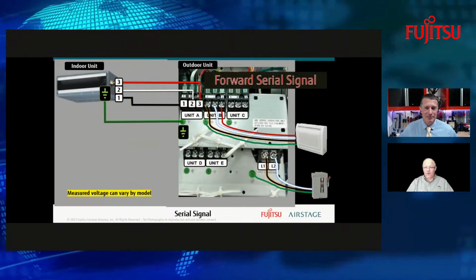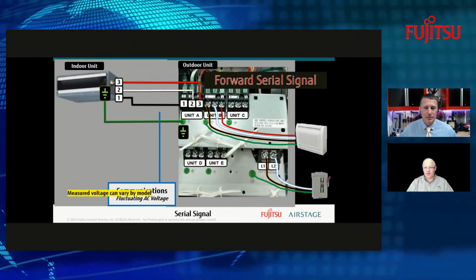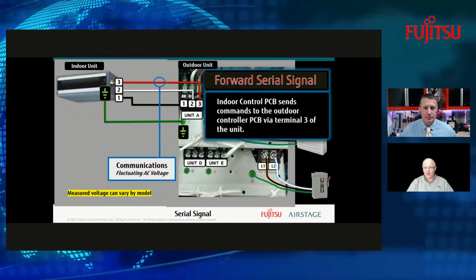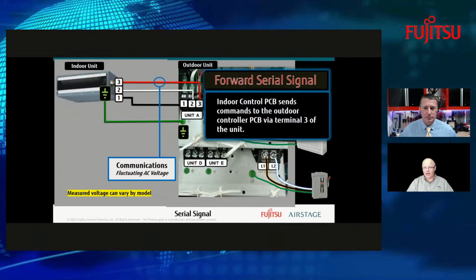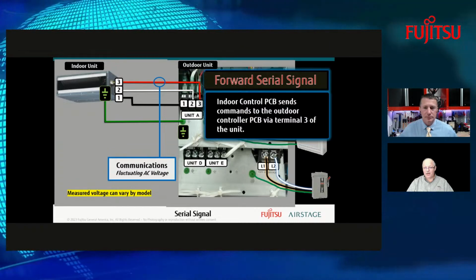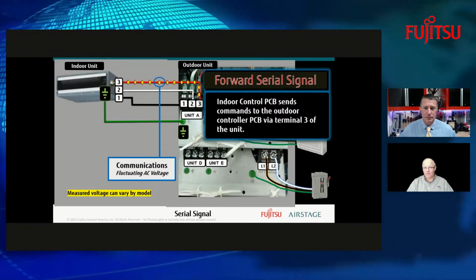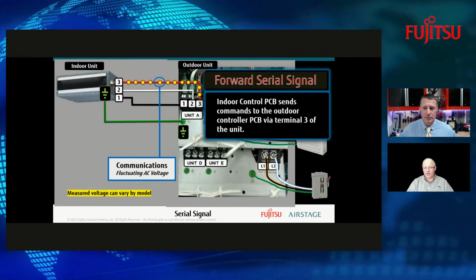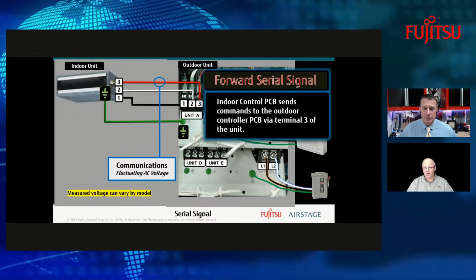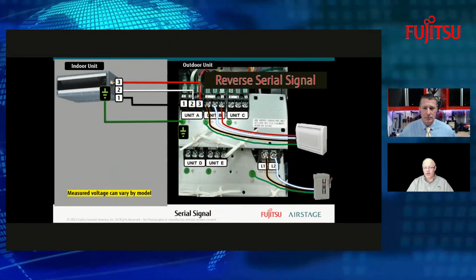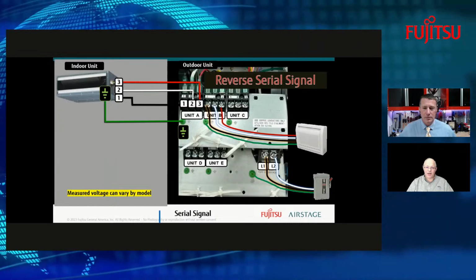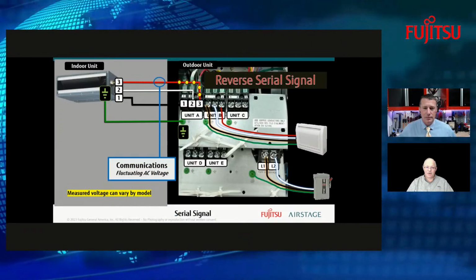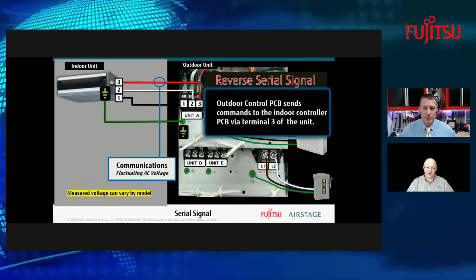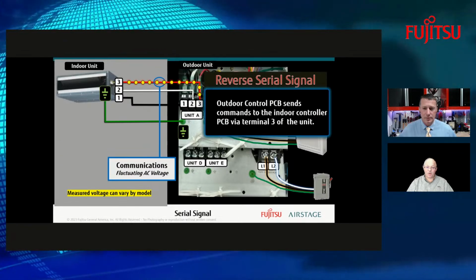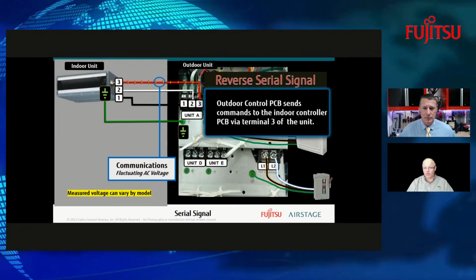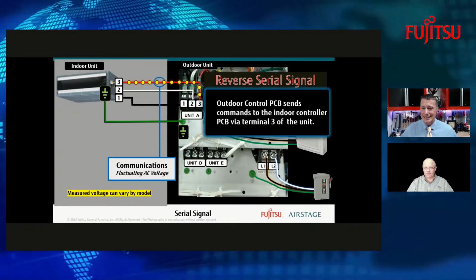Absolutely. So we have a forward serial signal that has to come, and in order for that indoor unit to talk back to the outdoor unit, it's going to send a forward signal from inside to the outside. So it looks like that. And so it's constantly giving information to the outdoor unit. And then we have a reverse signal, with the outdoor unit saying, okay, I got you. And so you'll have a reverse signal going back on number 3, back to the indoor. So they're really talking heavily on wire number 3. Okay. But I would read that as an AC voltage.